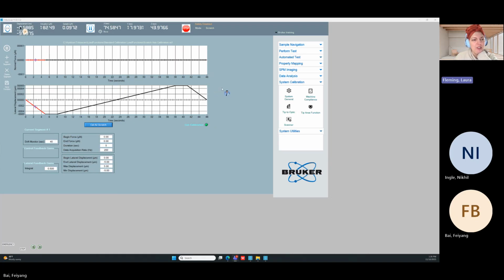So here, we've looked at this before: displacement, actuation, and sample. This is the sample force we've been using to determine if we were in contact or not during imaging. Now, there is an X parameter here. You can see it's moved to that imaging position of negative 9.9 as expected. It also updated your mode to scratch mode. So we turn on the scratch axes and it immediately moved to the imaging position. It's a good sign. It means it's actuating well, it's moving well. So that's what we're looking for.